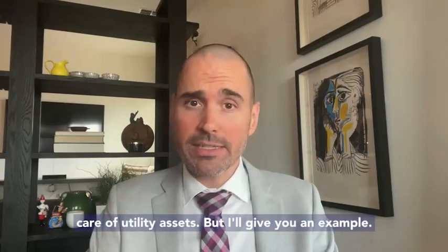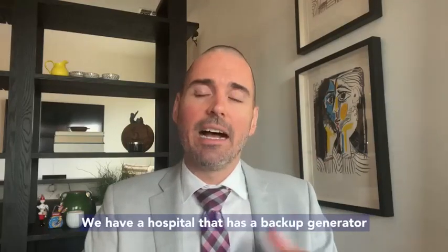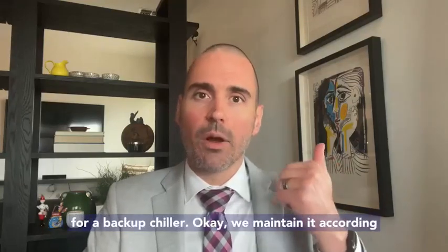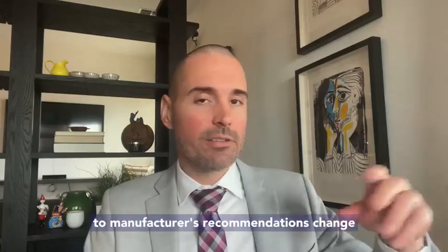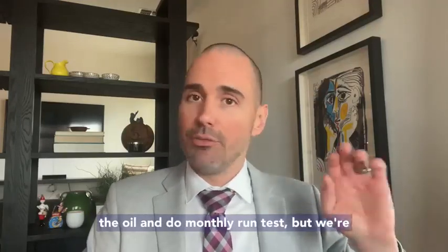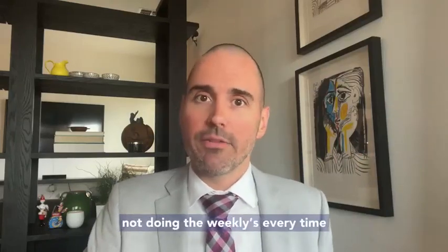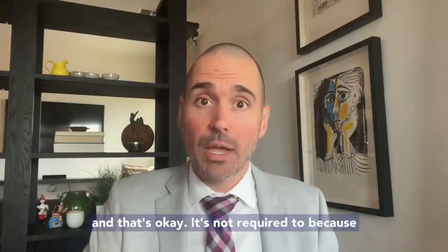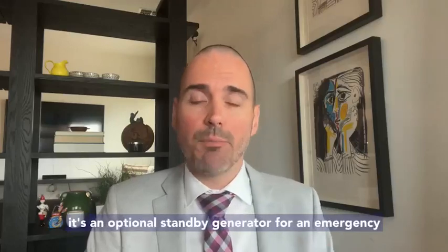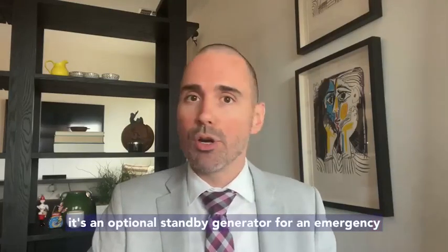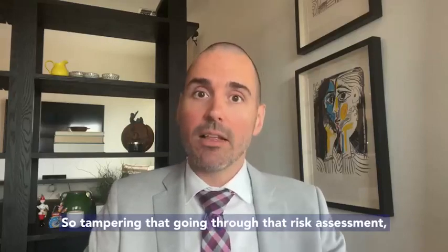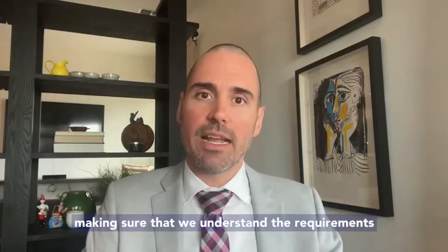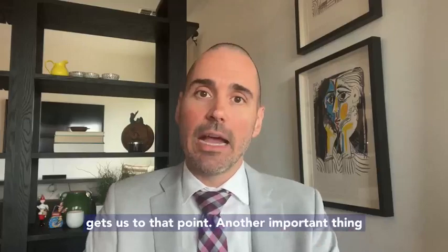But I'll give you an example. We have a hospital that has a backup generator for a backup chiller, okay? We maintain it according to manufacturer's recommendations, change the oil, and do monthly run tests, but we're not doing the weeklies every time. And that's okay. It's not required to because it's an optional standby generator for an emergency situation only. A backup to a backup, right? So going through that risk assessment, making sure that we understand the requirements, gets us to that point.